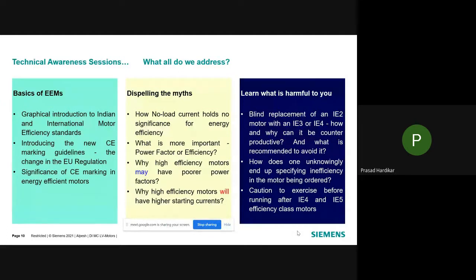Then we explain why high efficiency motors may have a slightly poorer power factor compared to a standard efficiency one, and give a rigorous mathematical and circuit-based proof as to why high efficiency motors will have higher starting currents, and why that should be kept in mind when you go for higher efficiency motors.